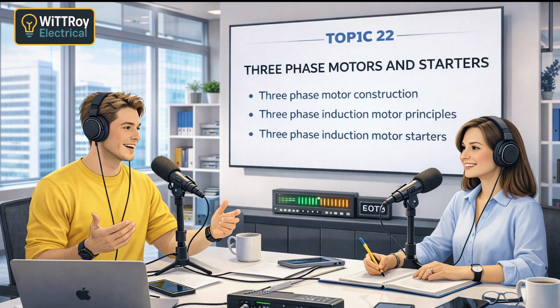No worries. Now we're talking about motor starters and what they actually do beyond just turning a motor on and off. Yeah, I always thought a starter was basically just a switch. That's very common, so you're not alone there. But a motor starter actually provides several layers of protection, and those protections are just as important as the starting itself. Okay, so it's doing safety stuff in the background. Exactly. Let's start with overload protection, because that's probably the most important one to understand.